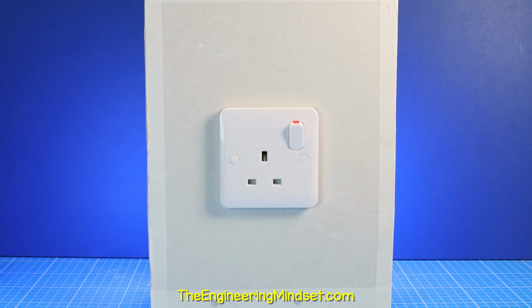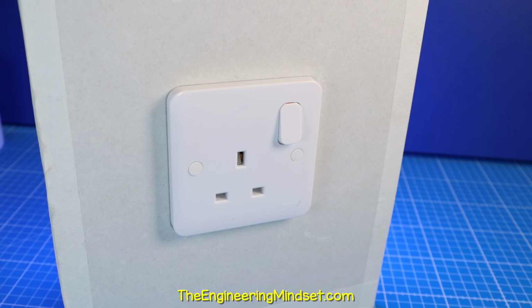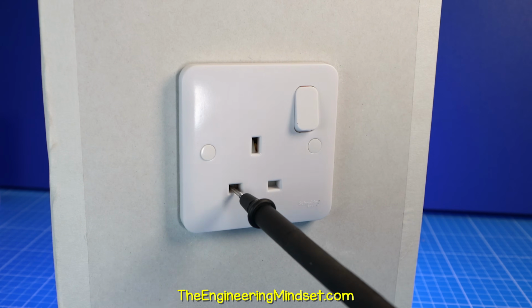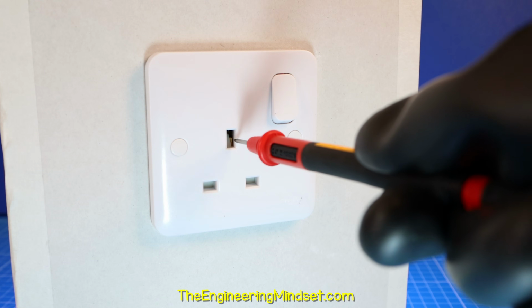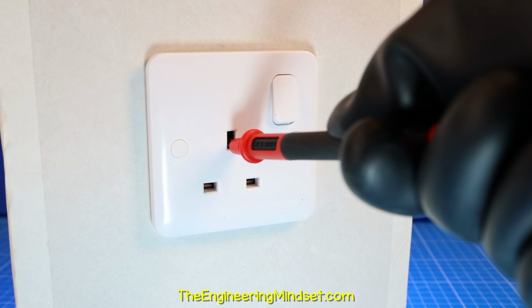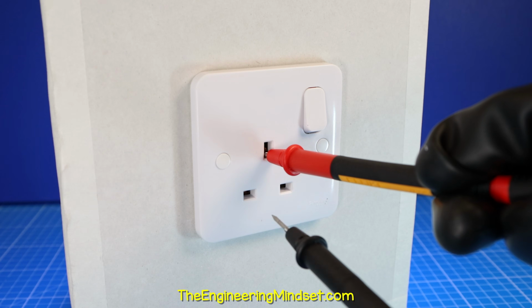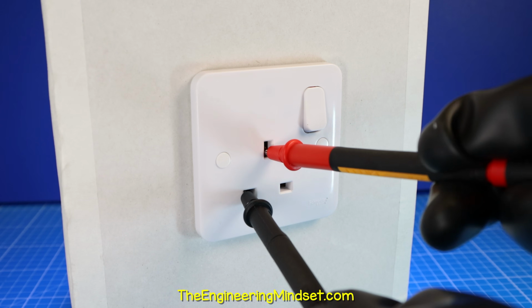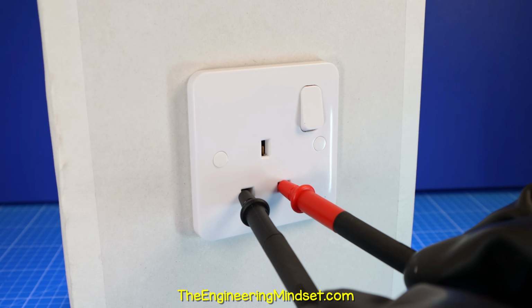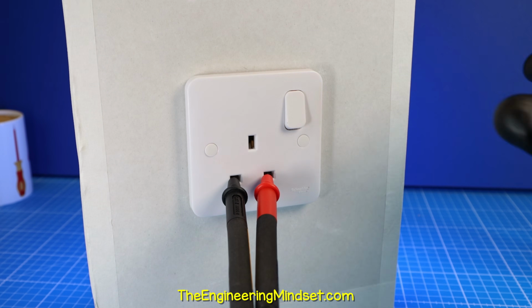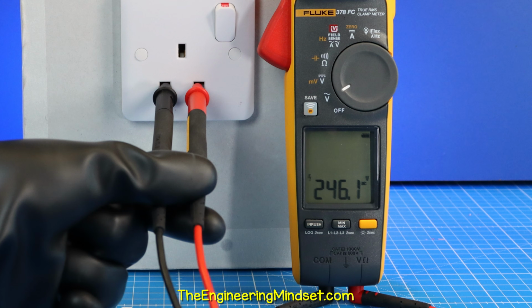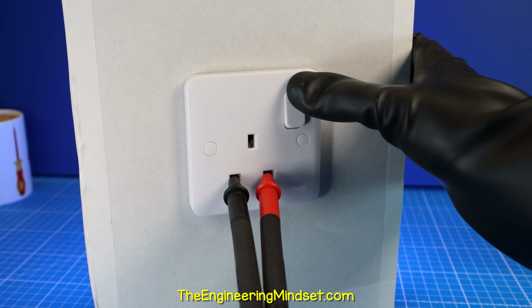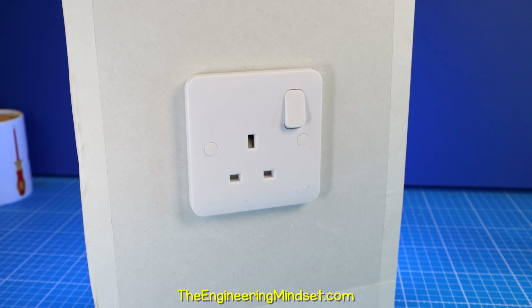For British circuits, switch the socket off first. We also find a safety screen with these, so place the red probe into the earth terminal and push down to open the safety screen. Then place the black lead into the neutral terminal and then the red lead into the live terminal. When safe to do so, flip the switch and the meter will display the value. Then flip the switch and remove the red probe and then the black probe.